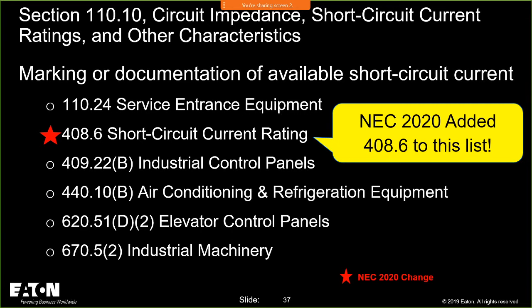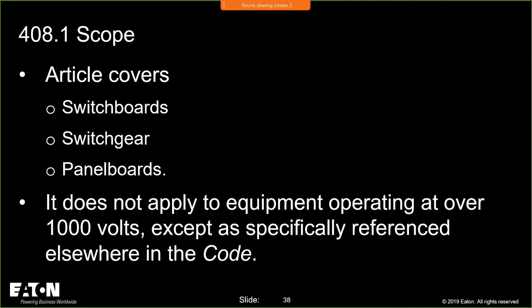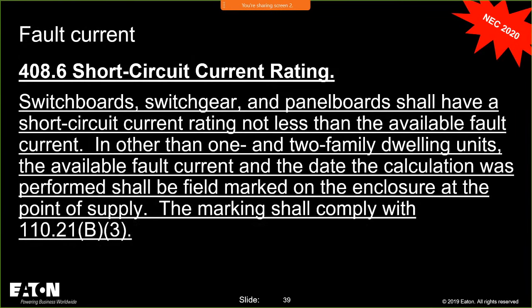Now, what's new for the 2020 cycle is 408.6, the section titled Short Circuit Current Rating. 408.6 is in part one, because 408 is separated into parts, which is a general requirement. The scope of 408.1 covers switchboards, switchgear, and panelboards, but it doesn't apply to equipment operating over 1,000 volts except as specifically referenced elsewhere in the National Electrical Code. So this marking is general for 1,000 volts and below equipment.